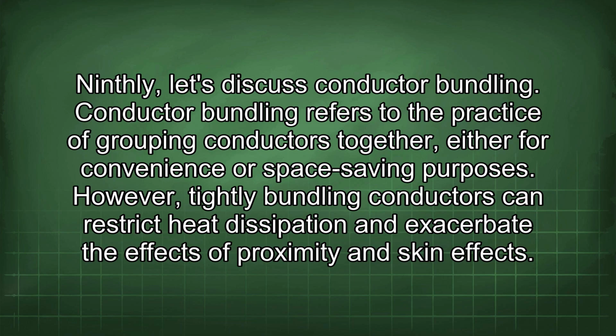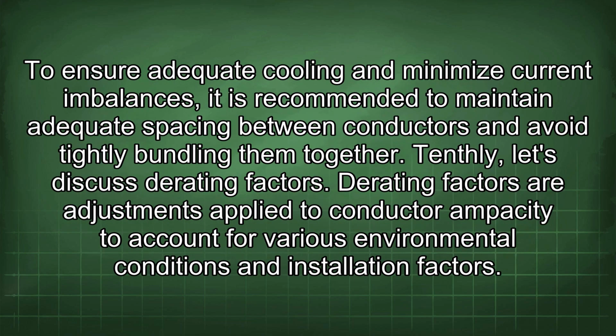Ninthly, let's discuss conductor bundling. Conductor bundling refers to the practice of grouping conductors together, either for convenience or space-saving purposes. However, tightly bundling conductors can restrict heat dissipation and exacerbate the effects of proximity and skin effects. To ensure adequate cooling and minimize current imbalances, it is recommended to maintain adequate spacing between conductors and avoid tightly bundling them together.